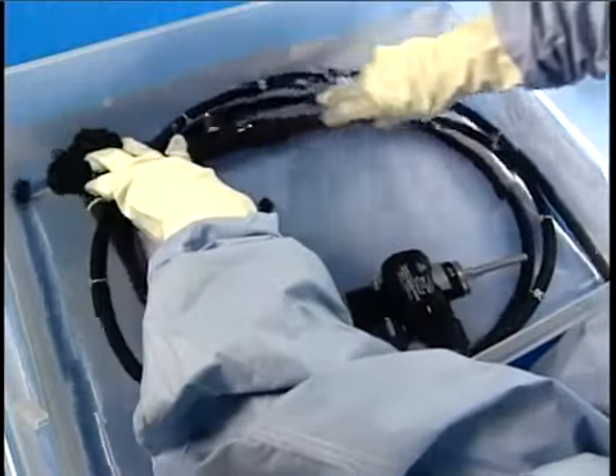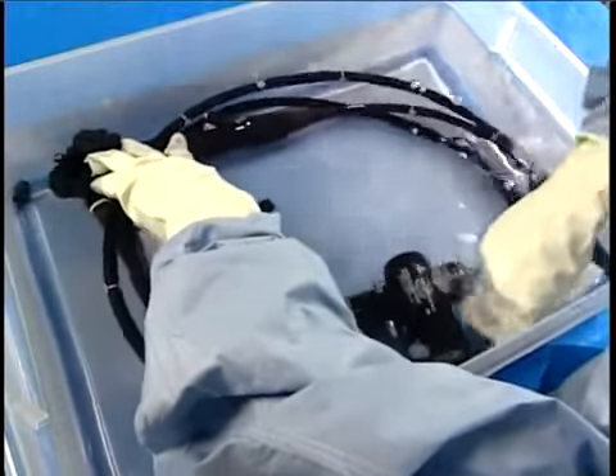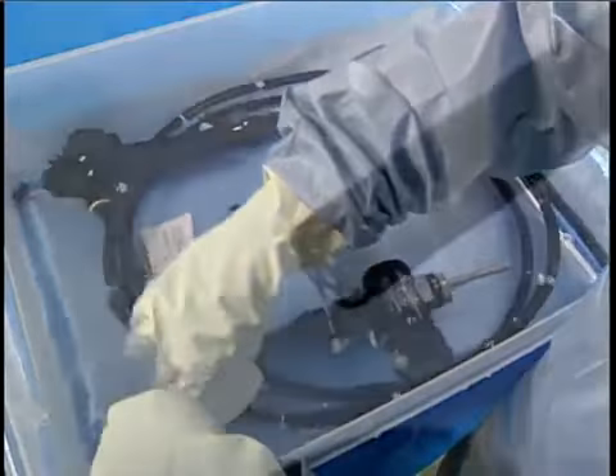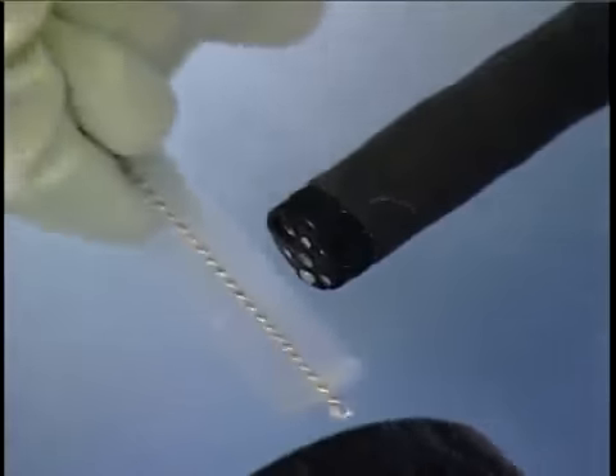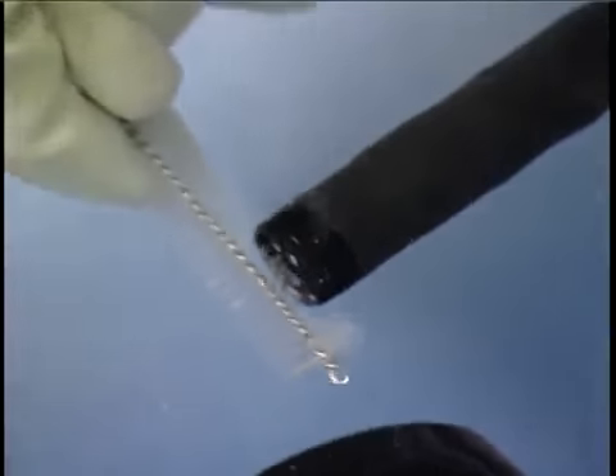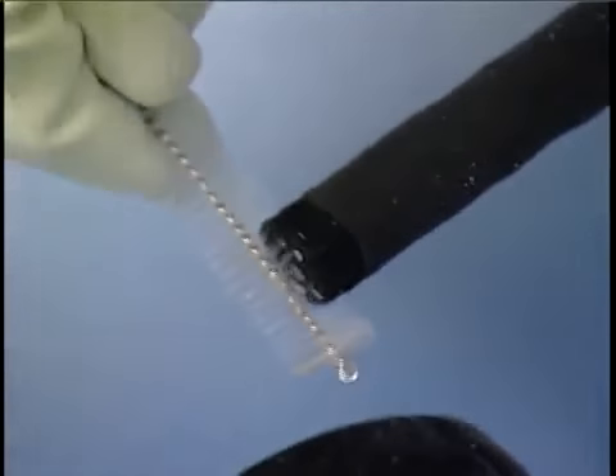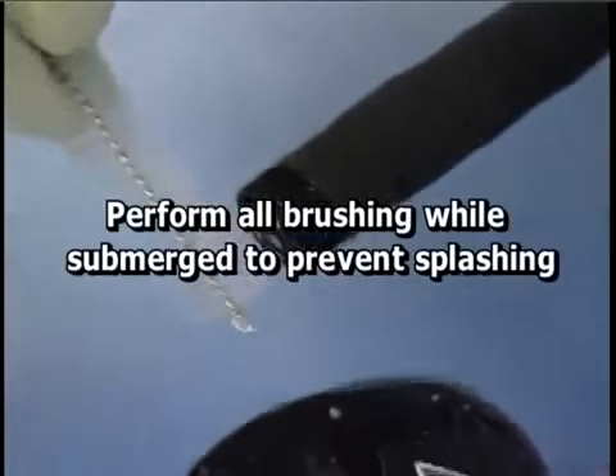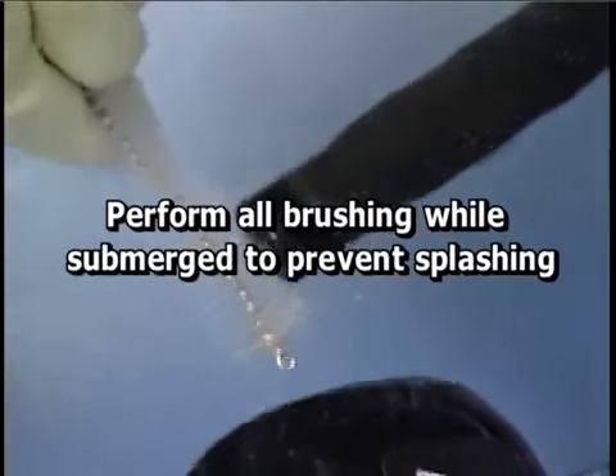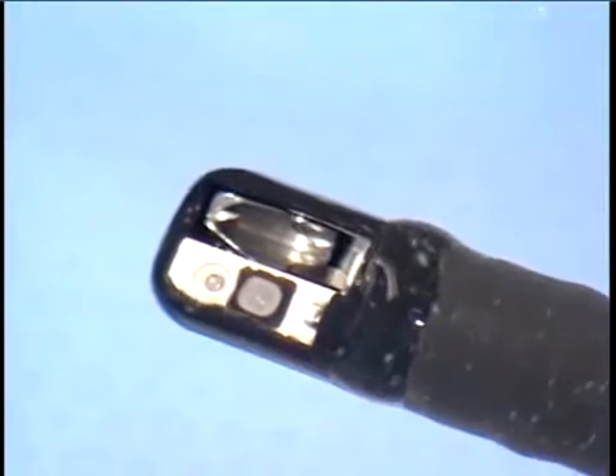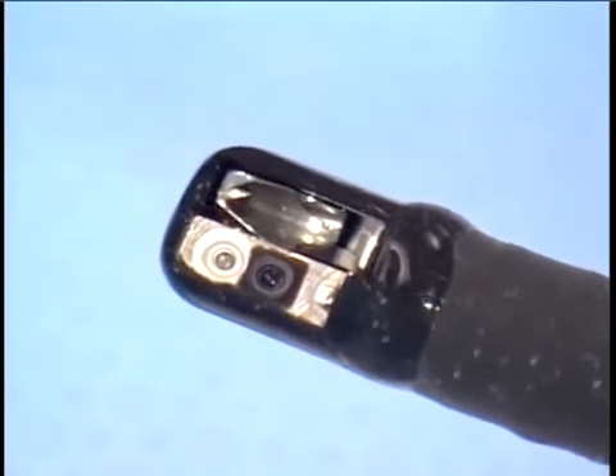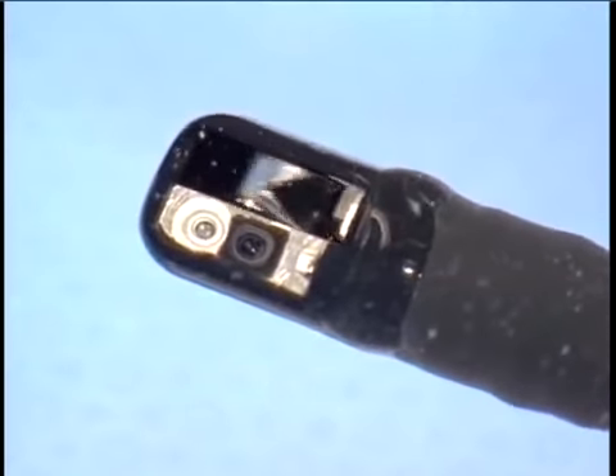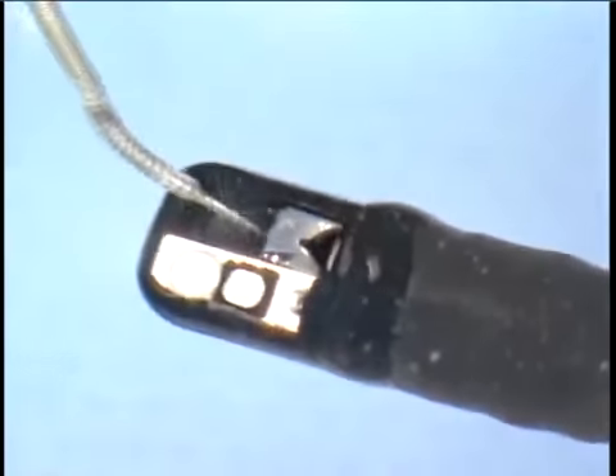Use a soft brush or lint-free cloth to clean the exterior surface of the endoscope. Pay particular attention to the distal tip and ensure that the air-water nozzle is free of debris. Take care not to scratch the small lenses. Perform all brushing while submerged to prevent splashing. If you are reprocessing a duodenoscope, raise the elevator and carefully brush around and under the elevator mechanism.